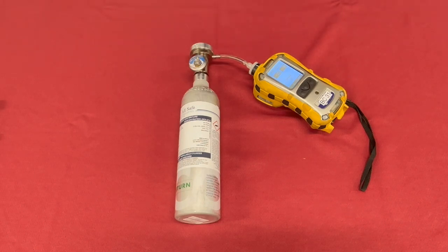Looking down, we still have 30 seconds to go. So the big thing to remember is the bump test is not a calibration. It does not adjust the meter, and if that gas does not come within 10% on the meter, it's going to fail that bump, and you'll have to go back and recalibrate the meter. No big deal, it happens sometimes. As far as the bump process, it's exactly the same though. It just doesn't last as long.